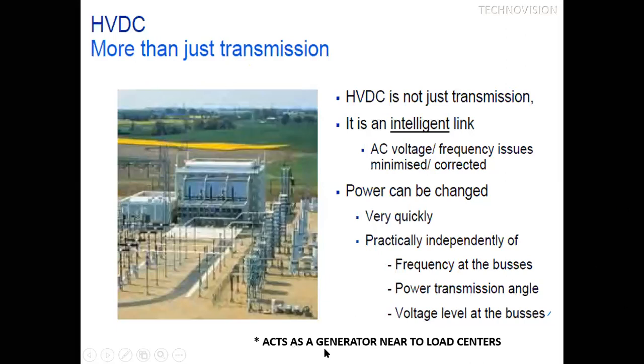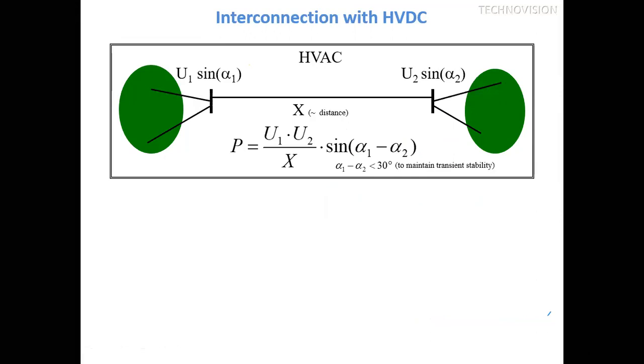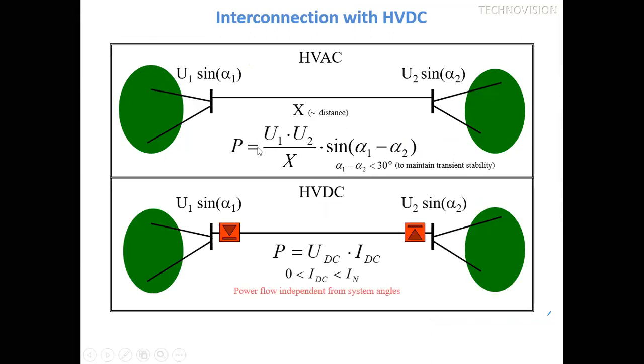So we have seen that HVDC acts as a generator near the load center. Now let us compare the power transmission capacity of HVDC and AC. We know that in EHVAC, the power handling capacity depends on the sending and receiving voltages, the distance of the transmission line, and the power angle, that is the difference between alpha 1 and alpha 2. For stability, the difference between these angles must be less than 30 degrees. For HVDC, the power handling capacity is DC voltage times DC current. So the power in DC is independent of both end voltages, the distance, as well as the power angle. That is why we can achieve more stability in the HVDC system.